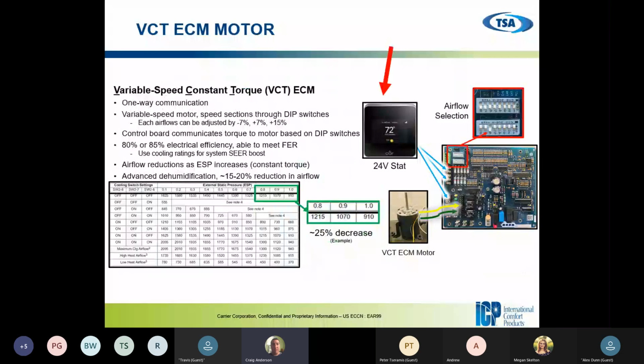This one here is a variable speed constant torque. This is in our 2-stage variable speed furnace. As you'll notice on the static pressure, because we're not communicating, we're using our dip switches to change the speeds in our motor. So our board is actually doing whatever we tell it to do. We can go from -7%, +7%, up to 15% of tweaking our motor speeds to allow for our temperature rise and our static pressures. But this one will only keep us at a constant torque because it's not communicating. So you'll notice that our CFMs will decrease depending on our static pressure and our ductwork.